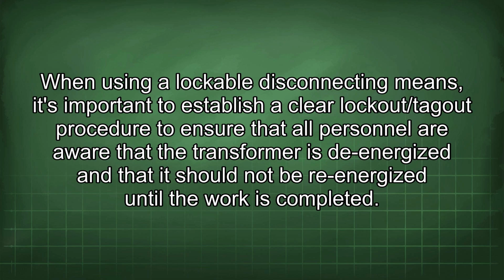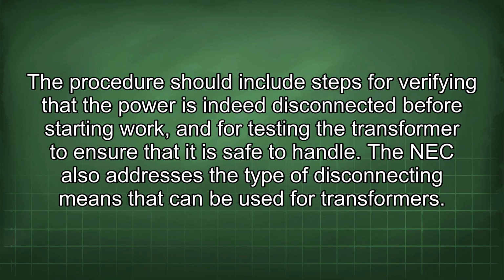When using a lockable disconnecting means, it's important to establish a clear lockout/tagout procedure to ensure that all personnel are aware that the transformer is de-energized and that it should not be re-energized until the work is completed. The procedure should include steps for verifying that the power is indeed disconnected before starting work, and for testing the transformer to ensure that it is safe to handle.